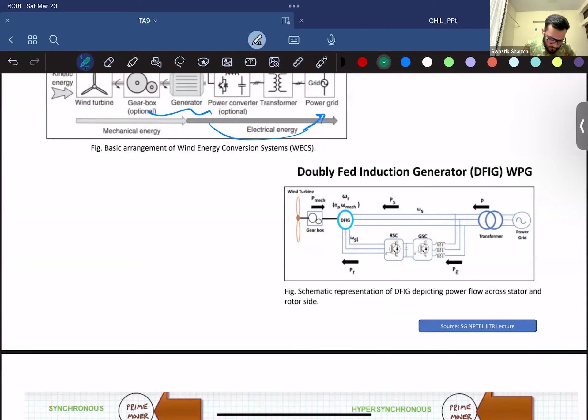So it has this dual energy input. The reason this is done is because usually wind speeds could be at synchronous level, so it can be at 50 hertz frequency, making your rotor and stator produce currents at 50 hertz. It can be super-synchronous, fast enough, more than 50 hertz frequency, or subsynchronous, lower than 50 hertz frequency, to produce currents at less than 50 hertz frequency.